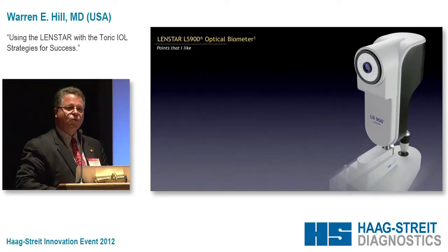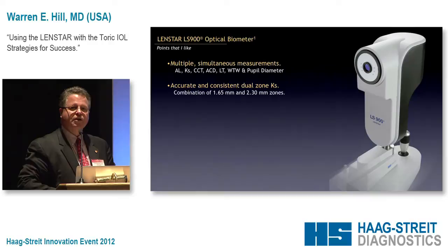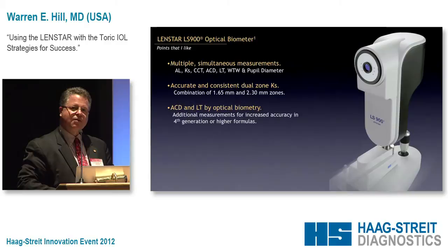With one button push, we get a lot of important and very accurate information. I'm going to talk specifically today about the Ks — this dual-zone auto keratometry. It's a unique and consistently accurate feature. Also, the anterior chamber depth and lens thickness are measured by optical biometry, not a slit estimation — actual numbers measured by laser biometry. And if you're using something like the Olsen formula, this becomes a very critical component.